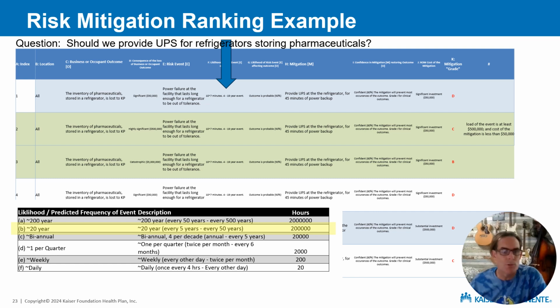Then the next thing that we would look at is the frequency of the event. So the event here is a power failure at the facility, and it has to be a power failure that lasts long enough for the refrigerator to go out of tolerance. So is that event happening every 20 hours, 200 hours, 2,000 hours, 20,000 hours, or 200,000, 2 million hours? Which is to say, is this a daily event, a weekly event, once per quarter? Is it biannual? Is it in that range of 5 to 50 years, or is it a 50-year, 100-year event, right? Well, obviously, it's not a biannual event, and it's not a 50-year event, and so we picked the range in the middle there, which is about a 5 to 50-year or a 20-year event, right?